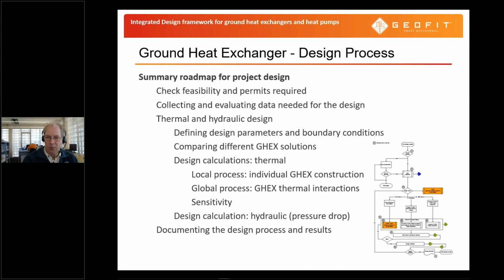And then we go into the thermal and hydraulic design of the system itself. So what are the design parameters and boundary conditions? Things like what temperature do we want to achieve in the ground source in heating and cooling operation, but also, for instance, a limit on drilling depth or other boundary conditions that we can think of. Then we want to take a look at the different ground heat exchanger solutions that we could apply. Are we going to go for a horizontal shallow one, or are we going to go for a vertical deep one? Once we've done all these decisions, we're going to do the calculations.